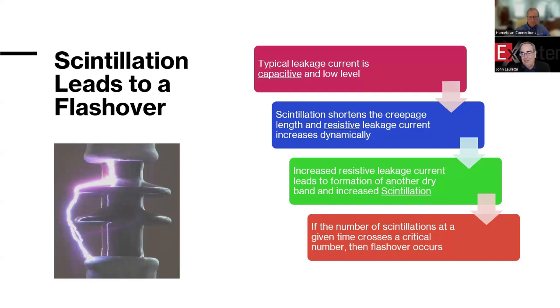And the issue is the scintillation comes from what's called a dry band arc. And that's a spot on the insulator that's been contaminated, gotten moist from dew, rain, snow, ice. A high axial current flows in that area on the surface, steams off the moisture, and bakes on that contaminant. And now you have something you can't wash off anymore, and it's going to present itself as an RF emission with the signature of an incipient failure.